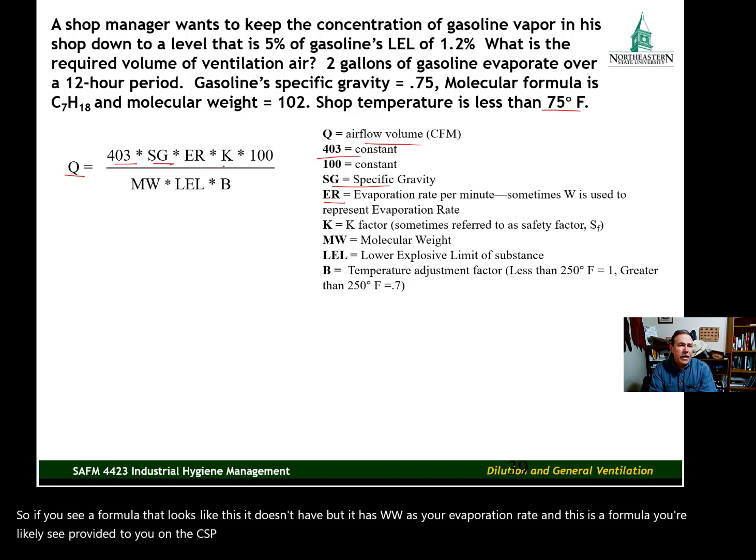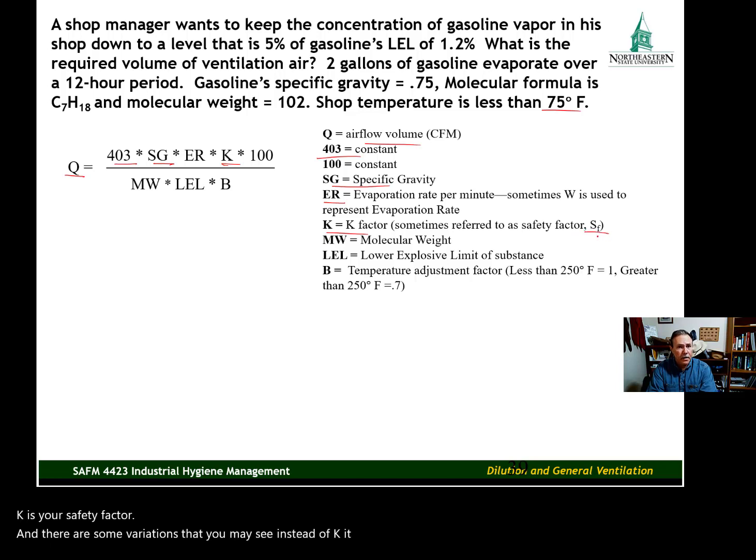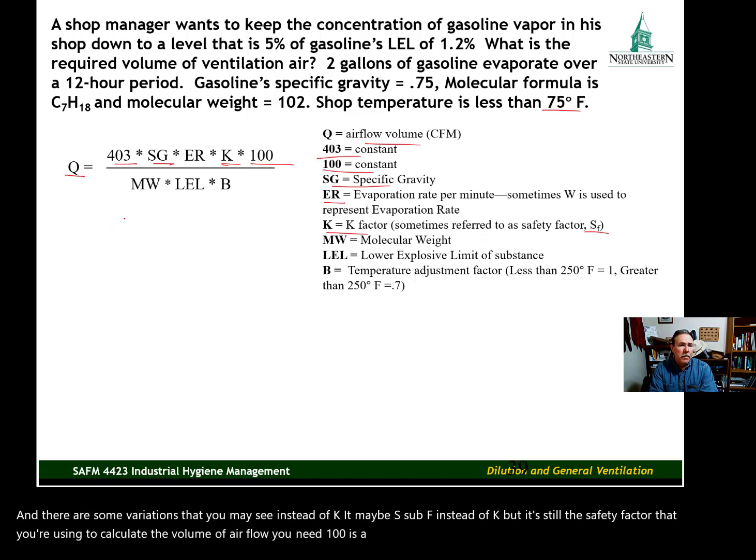K is your safety factor. There are some variations—you may see S sub F instead of K, but it's still the safety factor that you're using to calculate the volume of airflow you need. 100 is a constant, MW is molecular weight, and LEL is the lower explosive limit of the substance.